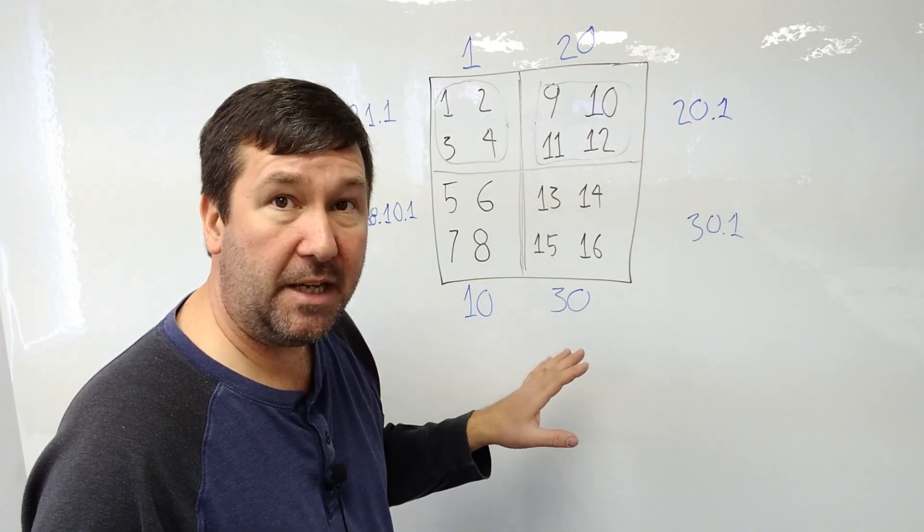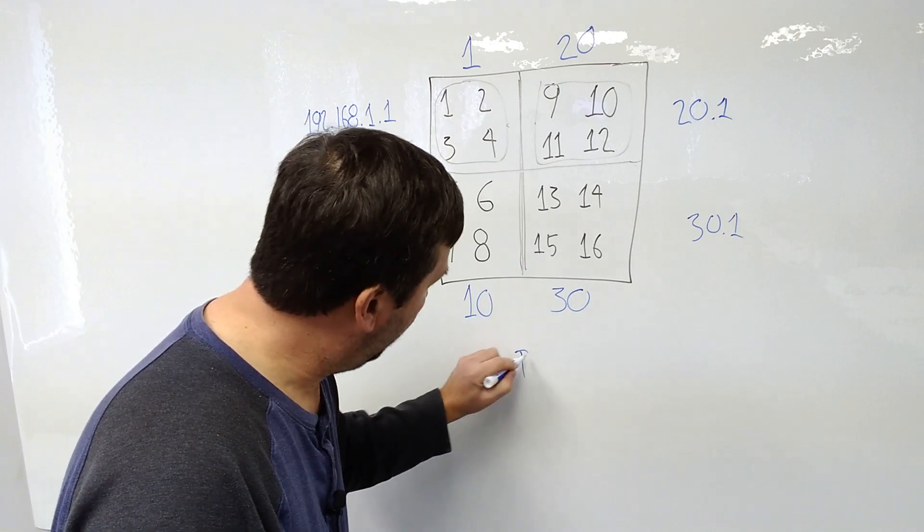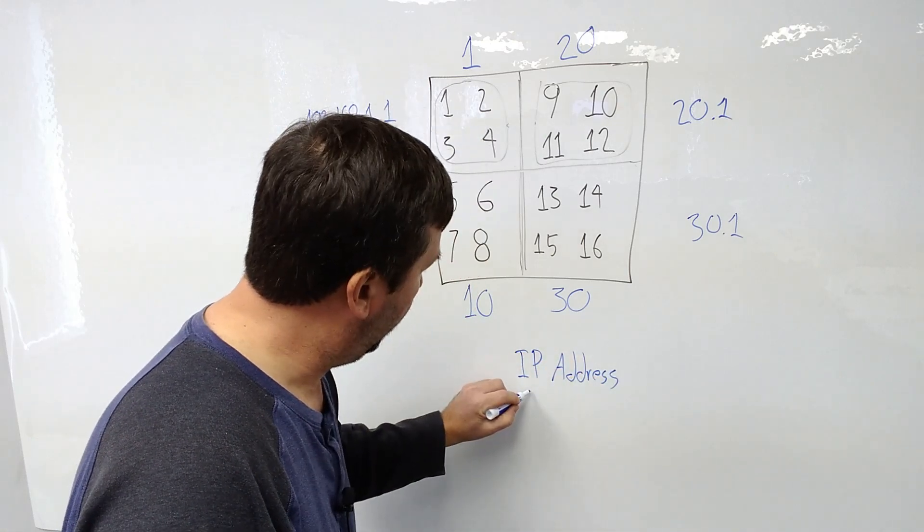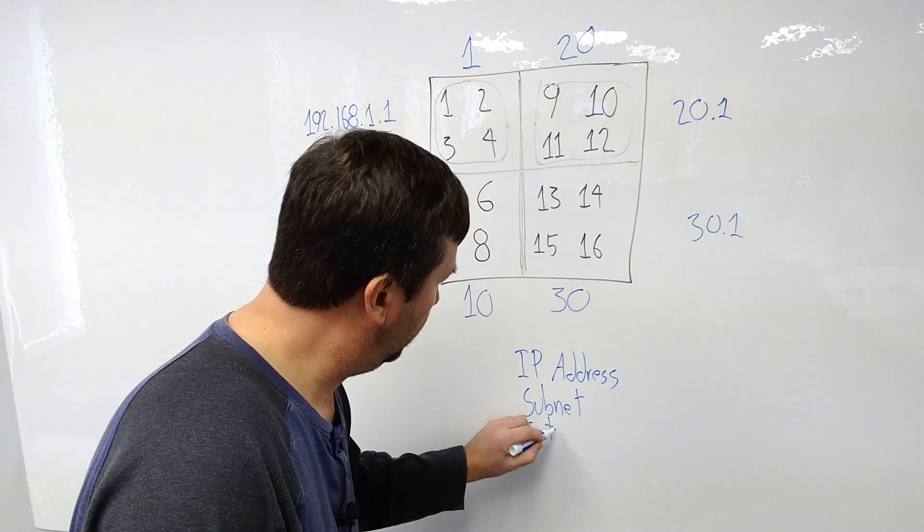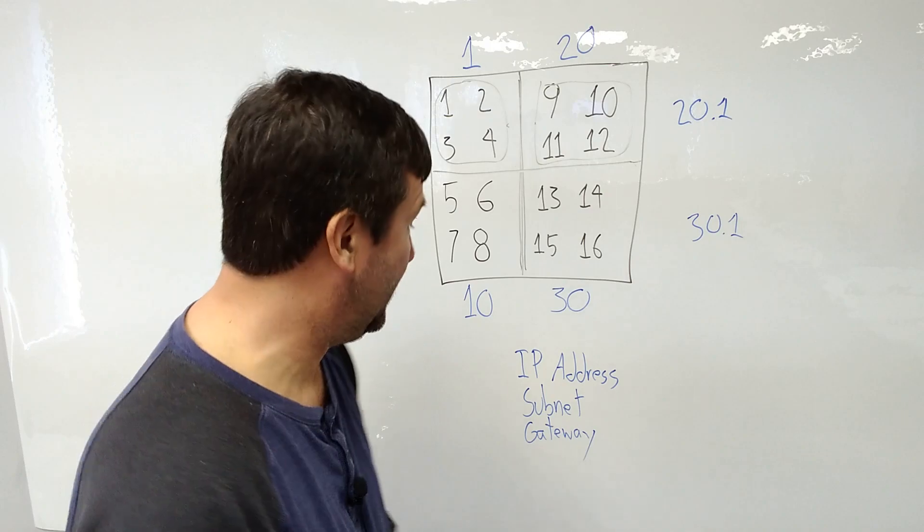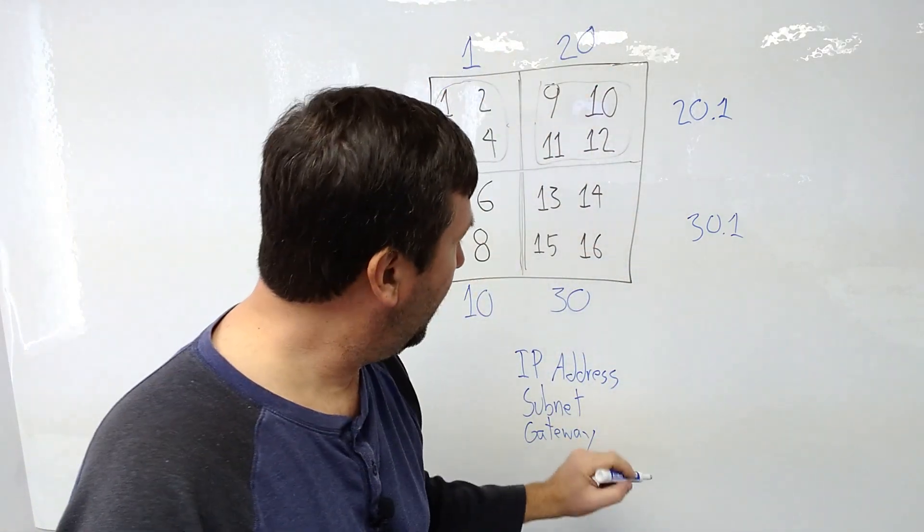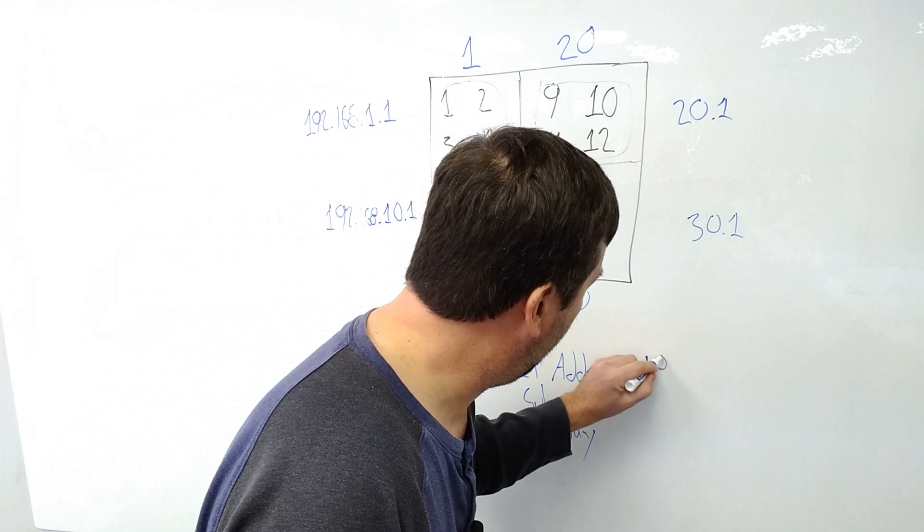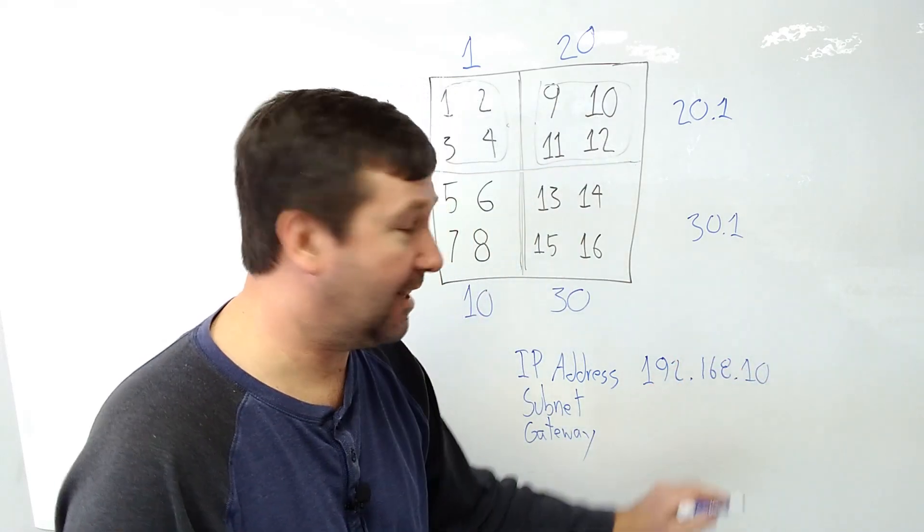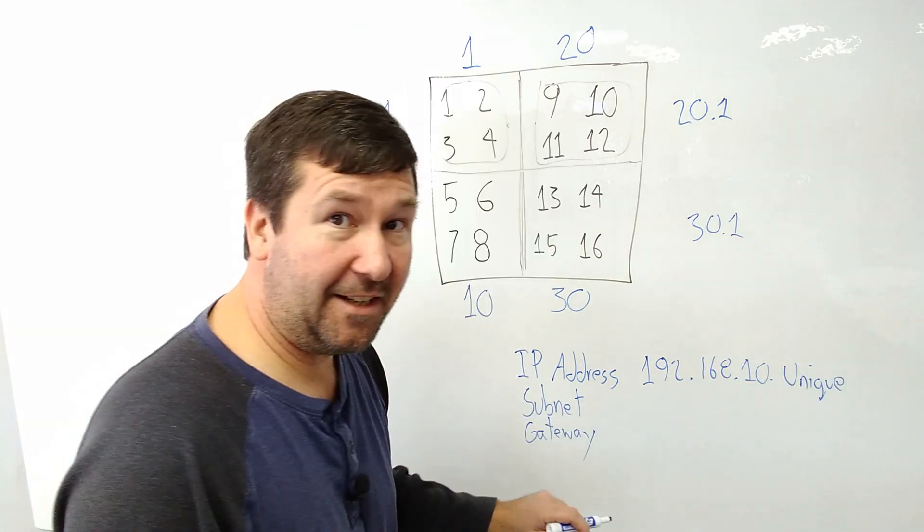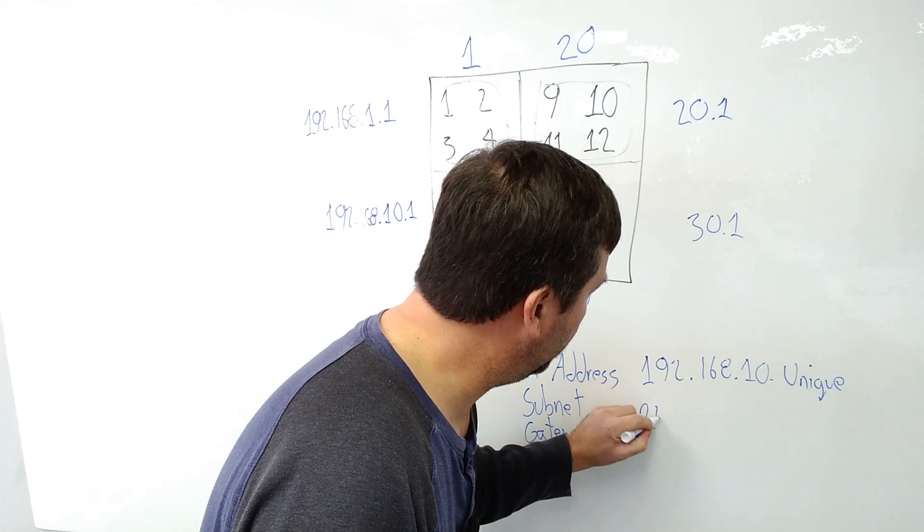So when we're entering our IP addresses, whether it be a PLC or our PC or any network device, we always have the IP address, a subnet, and a gateway. Now, again, this is Tim's rule, because this is not a networking class. But I've always said that these first three octets all need to be the same. So in the case of this one, we would need to be 192.168.10. And that last one needs to be unique. And then our subnet typically, again, typically, this is Tim's rule, this is not a networking class, the subnet would be 255.255.255.0.